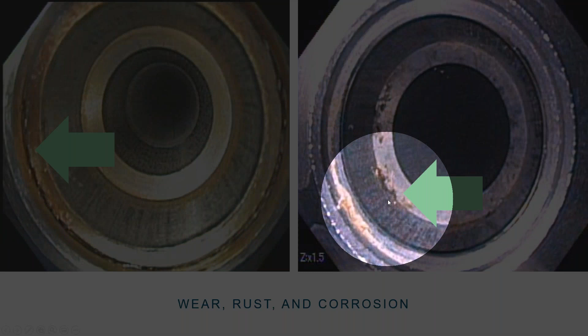These are really interesting. We bought about 200-some suction tips, brand new. When we looked inside with the borescope, we saw that at least 10% of them had issues. For example, these are the items on the thumb hole, and even this one further in: while they were drilling the thumb hole, the drill went too far and put a gouge inside the suction tip. Or this one, which was really interesting because it came in with a little metal shaving inside it. Trying to put it through the normal cleaning process, that little piece did not come out. So we marked it and made sure not to put it back in use.